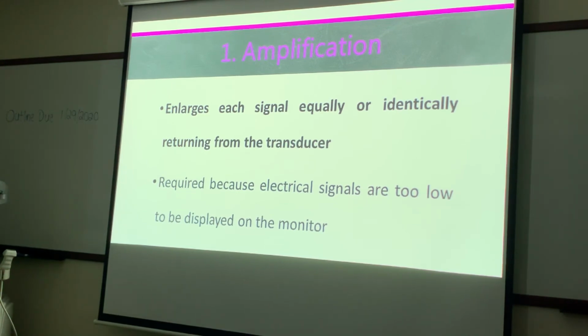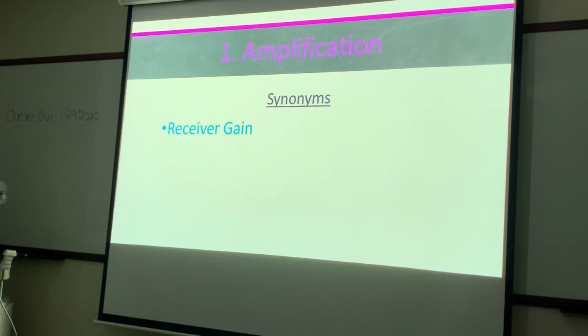Meaning that if I have a signal coming back at 10 and one signal coming back at 5, if all those signals are being doubled, now my signal is going to be 20 and 10, right? It's not going to amplify the weaker signals more than the higher signals. Each signal is going to be amplified to the same degree. Okay? So that's the amplification right there. Our synonym for that, guys, is going to be receiver gain. You guys know it as gain or the 2D button, right?